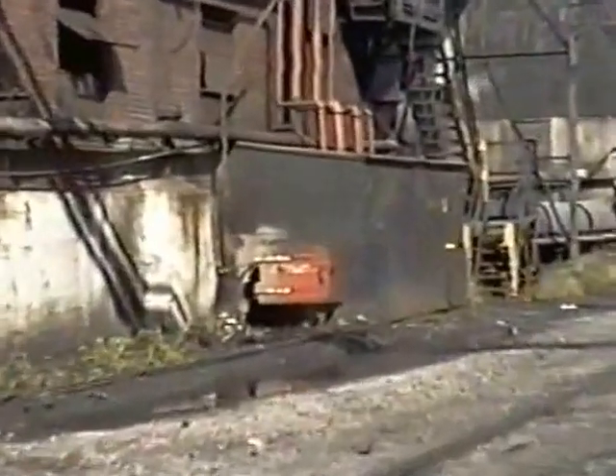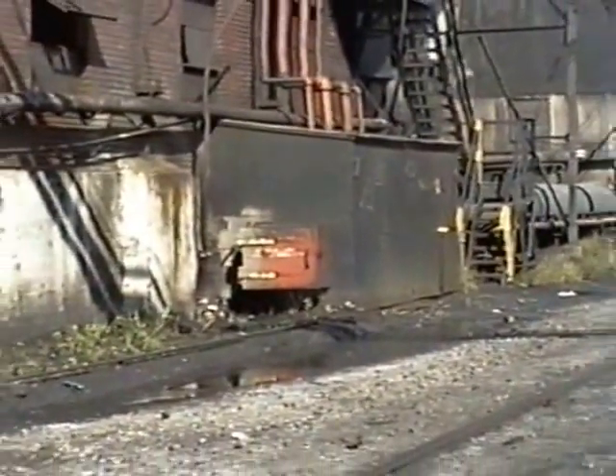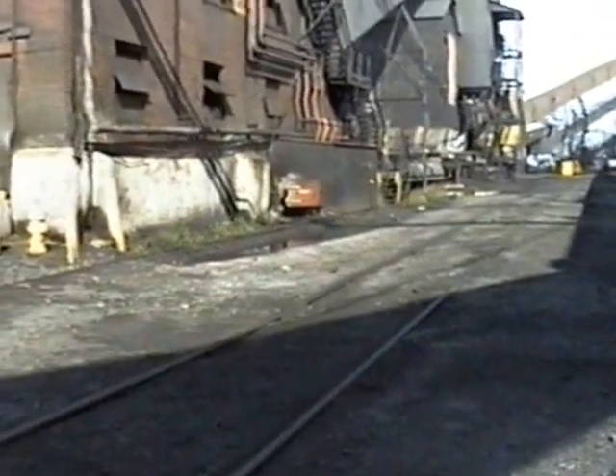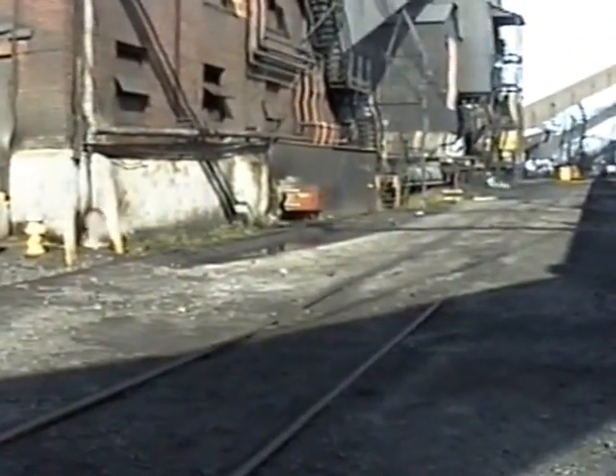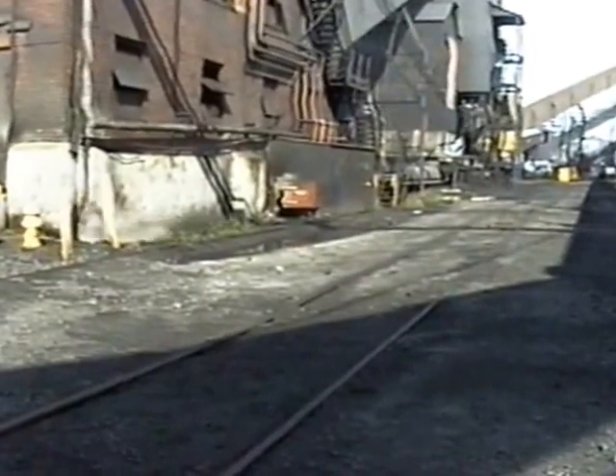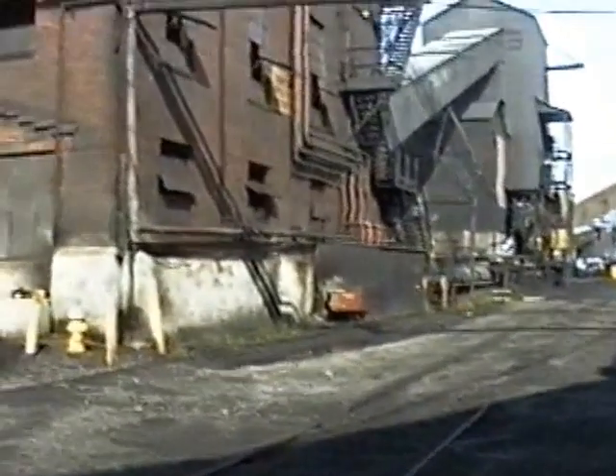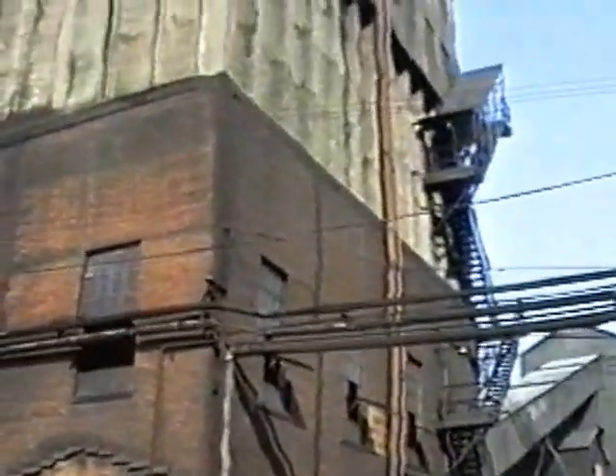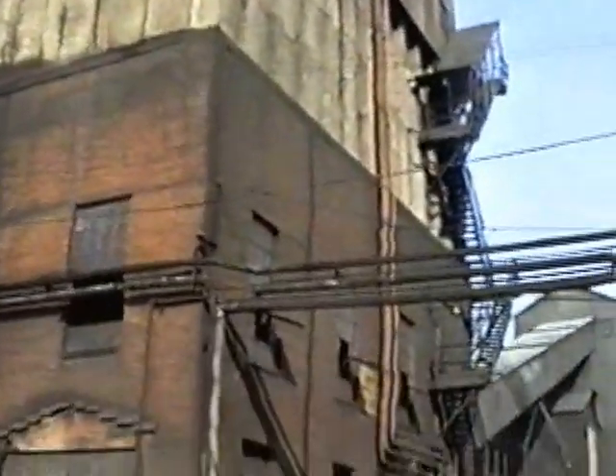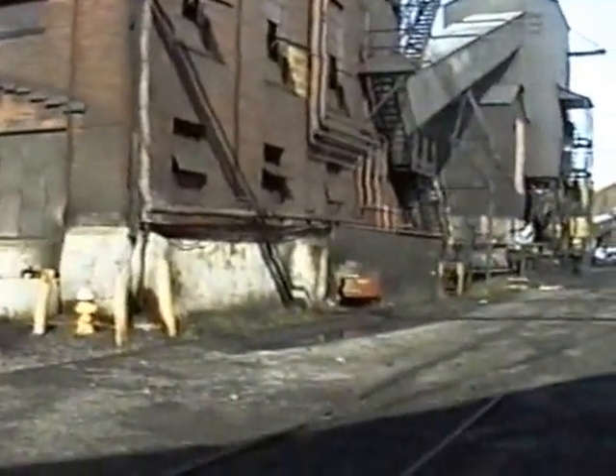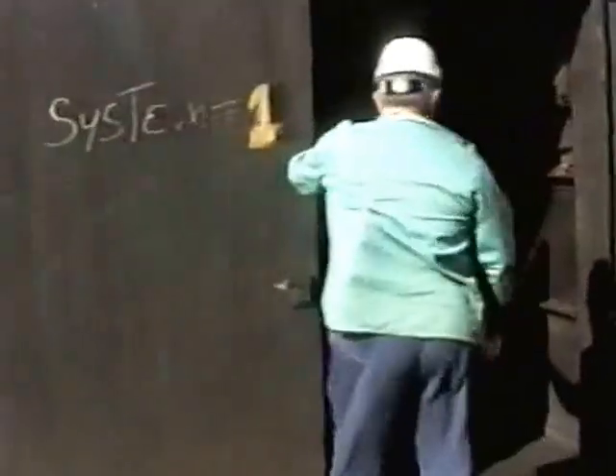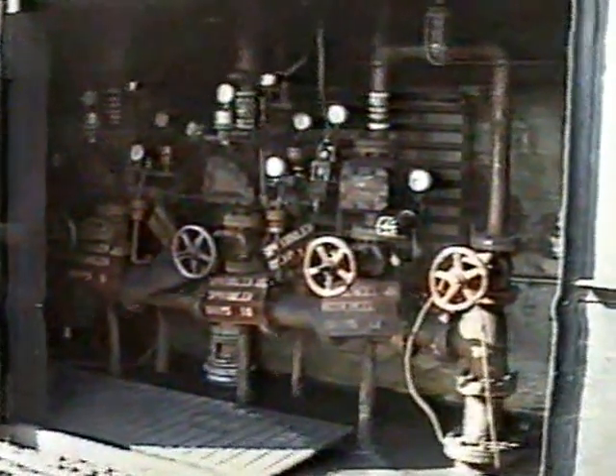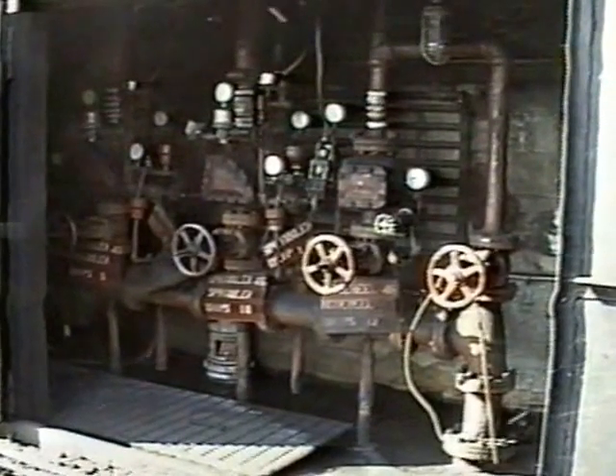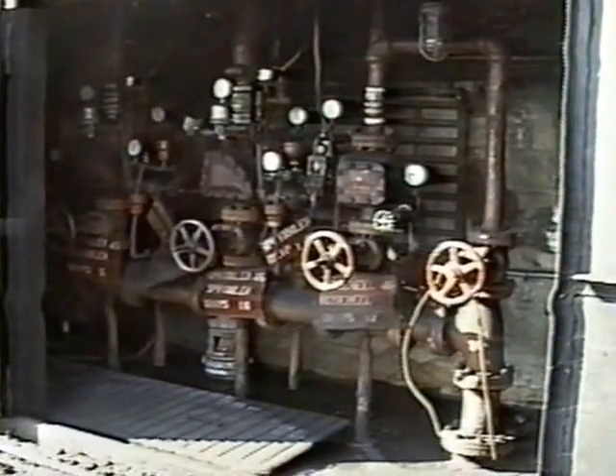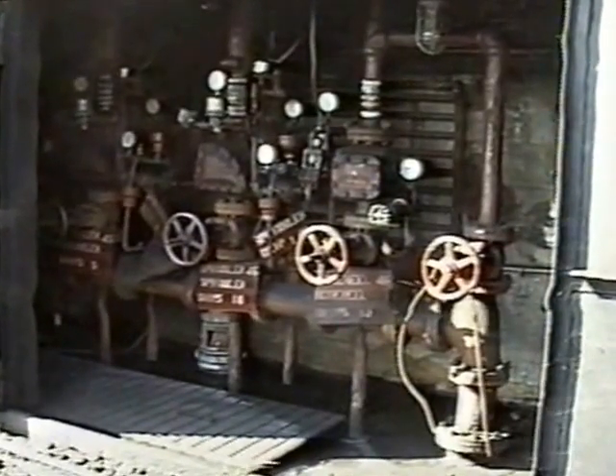Back at the east side, the building that you see in the foreground there has 4 more valves in it, the same configuration as we saw in the diesel fire pump building. The lines go all the way to the top of the building, and from there out to the various sprinkler systems and hose reels that are covered by this system. The extreme left side, the 2 sprinklers in the center, and the 2 hose reel systems on the extreme ends. The same design as the one that we saw in the diesel fire pump house.